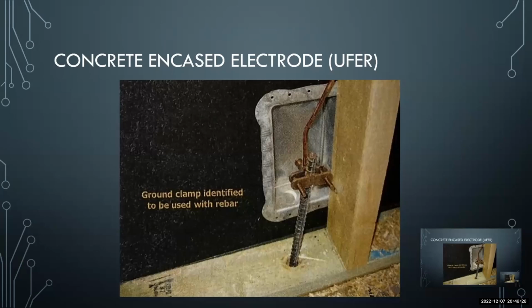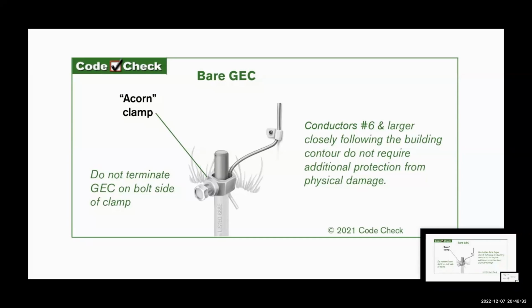Okay. Hey, Mike. Yes. Should that clamp be above ground or is it okay to be below ground? Because I've seen mostly it's below ground. It can be below ground if the clamp is listed for direct burial, and they'll have that marking on the clamp, and most of these are. As far as being above ground, the rods are typically 8 feet long, and the code says 8 feet is supposed to be in the ground. So if it's sticking up much more than 3 or 4 inches, then they could call you out on that and say you don't have 8 feet in the ground. A lot of guys in real tight jurisdictions will buy the 10-foot ground rods. But it can be above ground, and it can be below ground. But if it's below ground, the clamp has to be listed for direct burial.